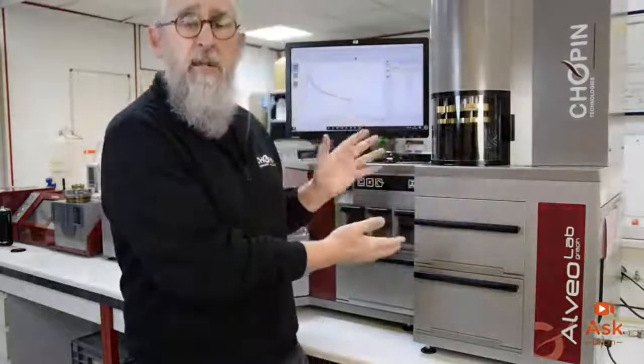When a machine is installed, training is provided, and there are videos explaining what to do and not to do. It is an analytical tool that requires care, but once you treat it properly you can get very precise results very rapidly — it's not like piloting a Boeing, it's very simple to learn. For maintenance, Chopin has an extensive network of distributors to help when results fall outside standard values. They will fix issues, send check samples to confirm problems, and calibrate accordingly — which is why the alveograph is a precise method.